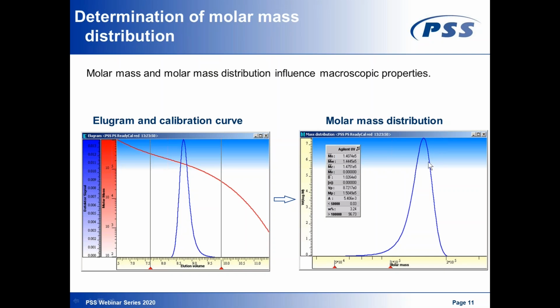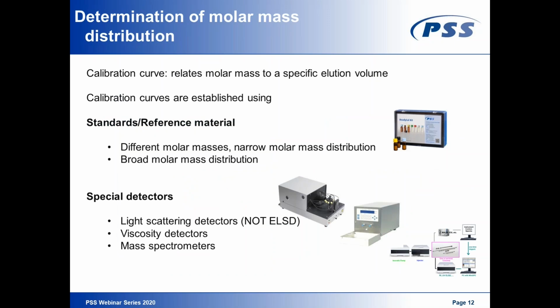We see the curve here. And of course, from this information, we can generate the molar mass averages, like the number or the weight molecular average. And we can also get, of course, the polydispersity of the samples. So once we have a calibration, or once we know which molecular weight elutes at which elution volume, we can get detailed information like the molar mass distribution, very detailed information. So how can I create such a calibration curve? There are in general two ways to create such a calibration curve. We can use standards or reference materials. We can use different molar mass standards with a narrow molar mass distribution or broad distribution standards. The other way is that we use specialty detectors like online light scattering detectors, viscosity detectors, or mass spectrometers.